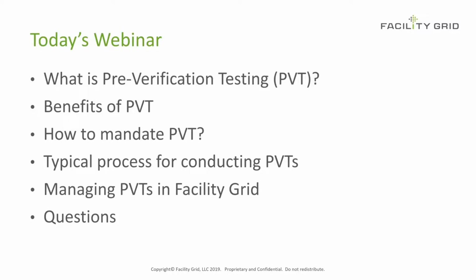So how often do you get to the job site to conduct functional performance testing and realize that this is the first time contractors are seeing the FPT procedures? Also, completion of the pre-functional checklists is typically used as an indicating factor of the equipment readiness for the functional tests. However, just because all the boxes are checked does not necessarily mean that the equipment is ready to perform according to the sequence of operations per the approved control submittals, which are typically used as a basis for the FPT procedures. One way to avoid this is by performing pre-verification testing.